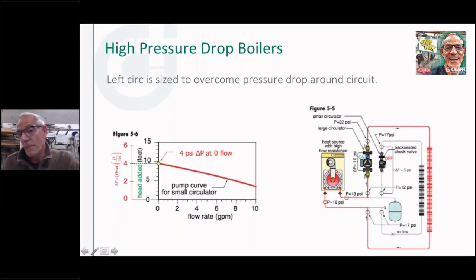Now let's take a look at a pump that might be on a circuit like that, and let's go over here and look at that little circulator, look at the pump curve here. And notice the circulator at this low flow, no flow condition can only develop about 4 pounds of pressure differential. And I've got 5 pounds here. So that circulator is never going to be able to pop open its check against the pressure that's against it here and be able to flow through that circuit. So therein lies the problem: if you do come up with a pump that can overcome your pressure drop in your boiler, in your circuit, and you have smaller pumps on that same boiler on that same distribution, you can see where you've got the problem with the high head. It's actually overpowering the small circulator there, and you're never going to get flow through that.